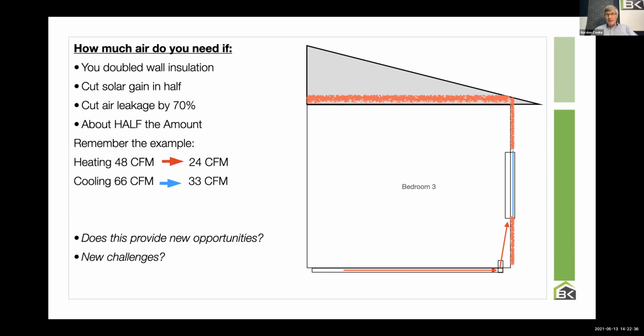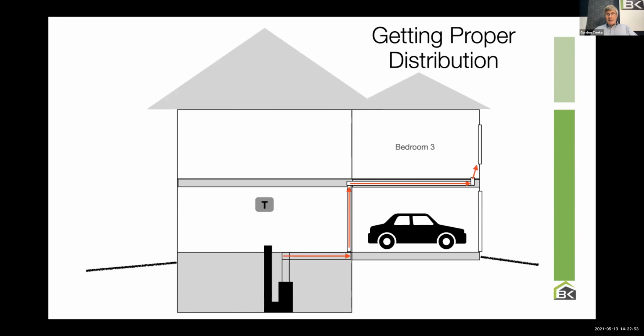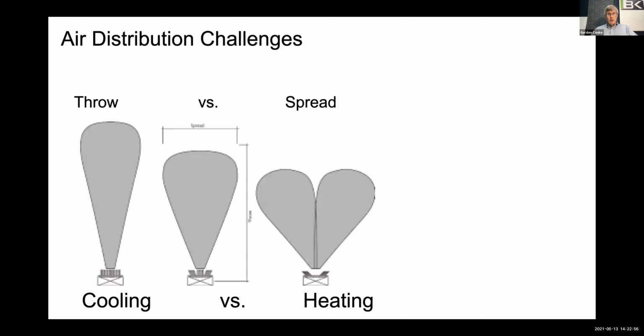That's really the lesson. And notice that the difference is now only 11 CFM between summer and winter. It's much easier to manage that than the 20 or 25 CFM that you need summer to winter when you don't have a high-performance house. So it's an opportunity, but it's also a challenge, if you will. So getting that proper distribution is what we're looking for.